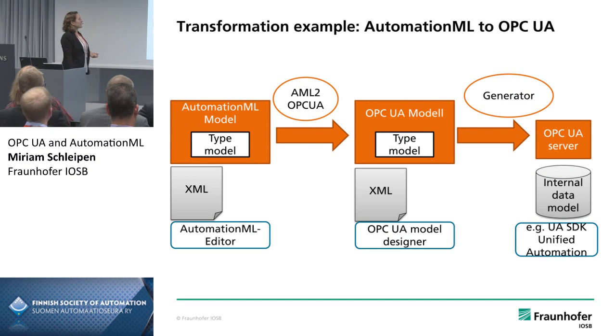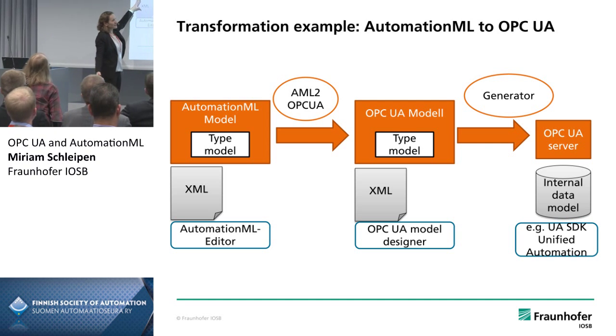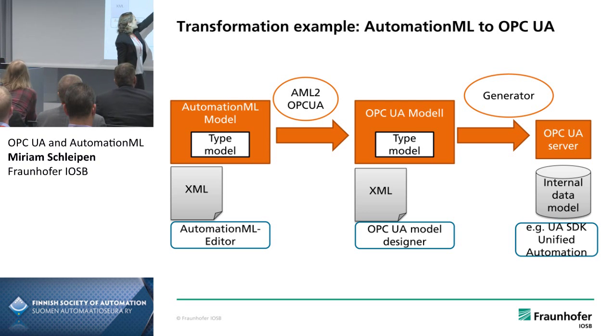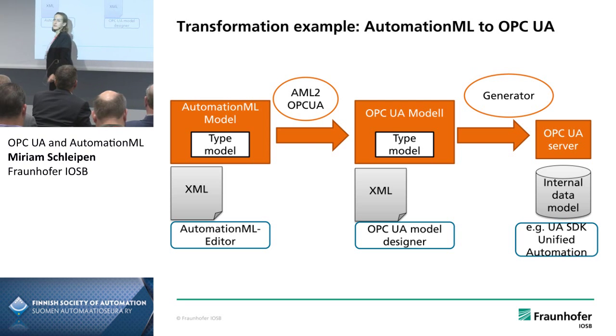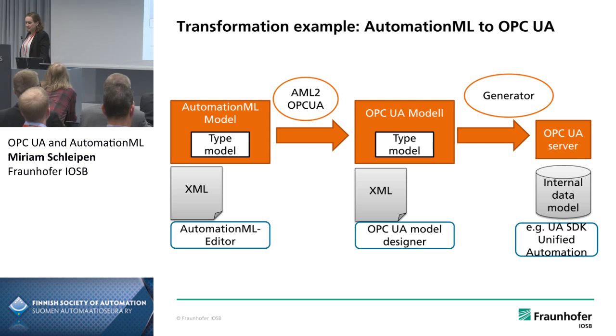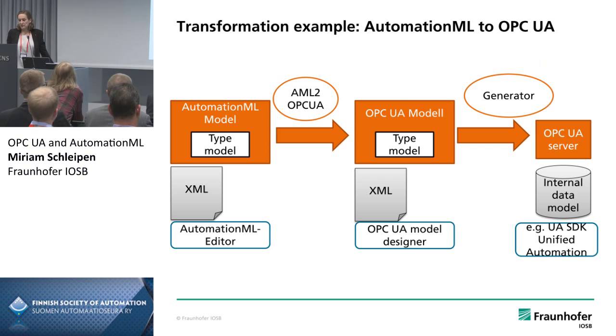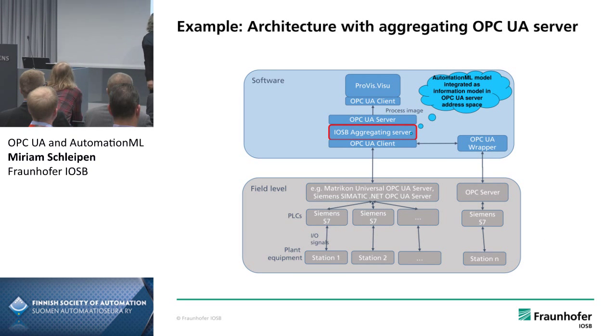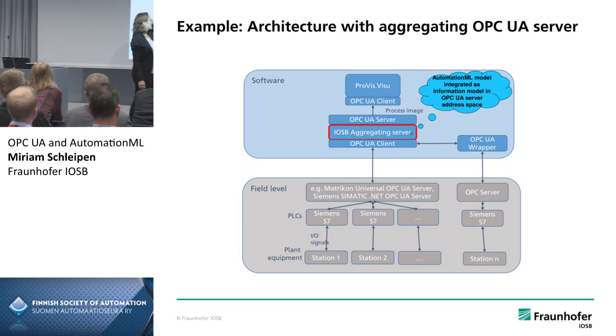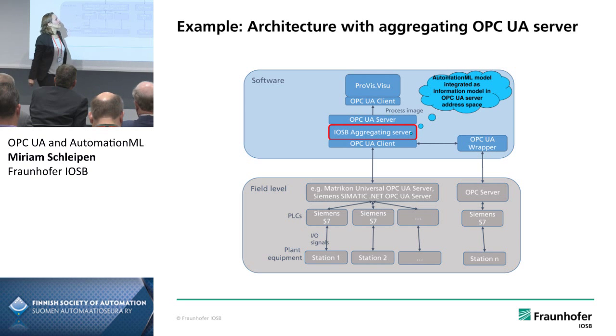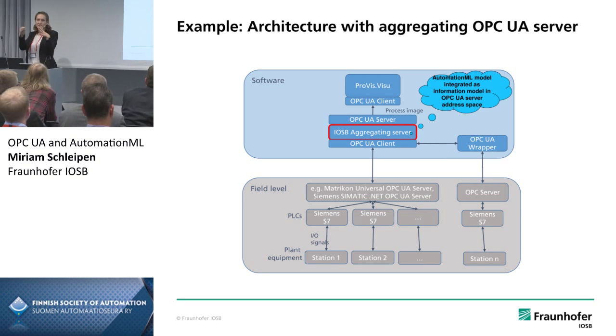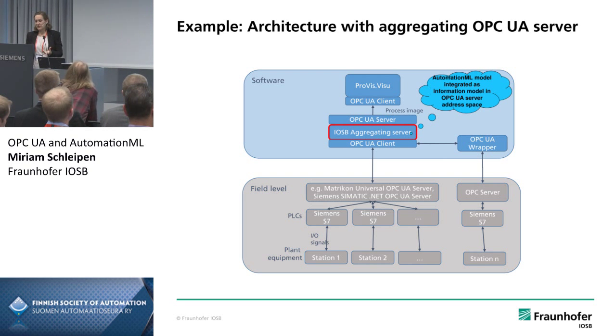To show how to use it: if you have an AutomationML model in XML, you translate it into OPC UA XML, then you can easily integrate it as an internal data model in an OPC UA server — for example, for aggregating servers or servers dealing with MES. For instance, if you have normal Siemens PLCs and an OPC UA server running above them, completely independent of the vendors, you could have an aggregating OPC UA server that gets all the data from all the PLCs and integrates them into the AutomationML model. Then you have a complete view of your plant — the planning data but also the online data related to it.